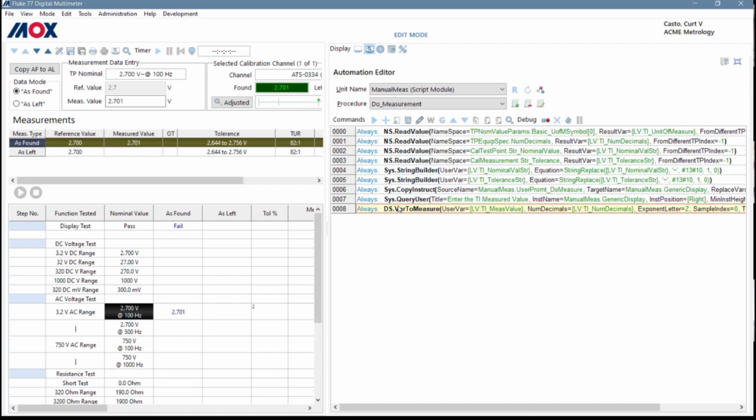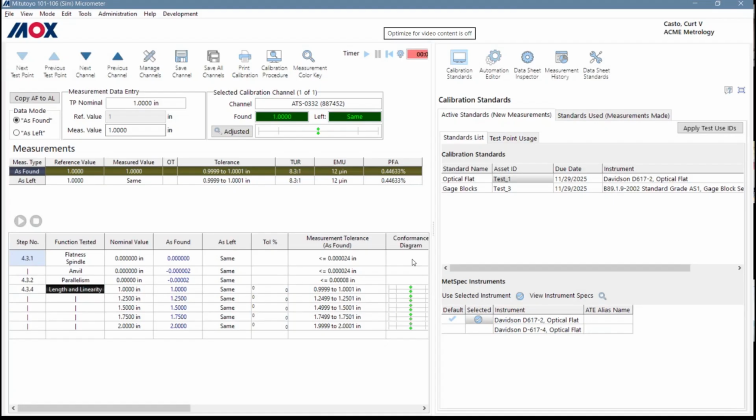This process is a lot better than any automation building that I've seen. I think I want to go back to the fact that you have the data sheet already. You're making a manual data sheet and using that information to create an automated data sheet, where I have not seen anyone do that. They have to start all over from scratch, and they'll take that manual sheet and look at it and say, oh, these are the test points we're trying to hit. And they'll write the script for those test points, where you could have any data sheet here and you have a wizard that's going to tell it, hey, this is the nominal value I need you to hit. This is the standard I need you to communicate to.